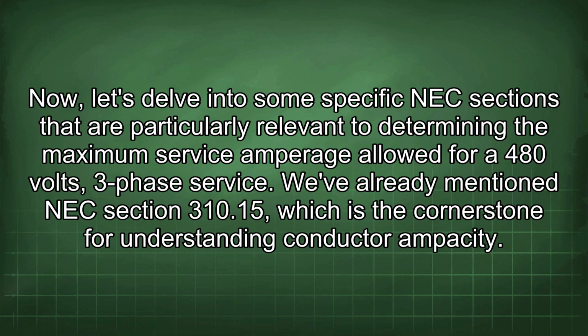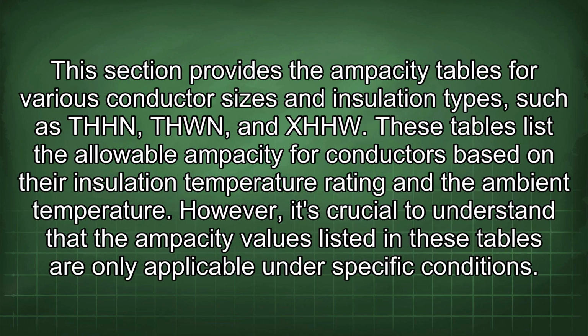We've already mentioned NEC section 310.15, which is the cornerstone for understanding conductor ampacity. This section provides the ampacity tables for various conductor sizes and insulation types, such as THHN, THWN, and XHHW. These tables list the allowable ampacity for conductors based on their insulation temperature rating and the ambient temperature. However, it's crucial to understand that the ampacity values listed in these tables are only applicable under specific conditions.